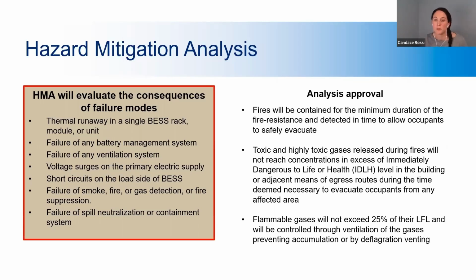So ultimately, the fire code official will approve the hazard mitigation analysis, assuming the points on the right hand of the screen have been met: that fires will be contained for a minimum duration of the fire resistance and detected in time to allow occupants to safely evacuate, that toxic and/or highly toxic gases released during fires will not reach concentrations in excess of immediately dangerous to life or health level in the building or adjacent means of egress routes during the time deemed necessary to evacuate, and that flammable gas will not exceed 25% of their lower flammability limit and will be controlled through ventilation of the gases.